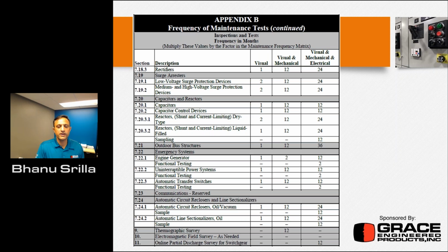So how does normal operation affect operator or maintenance staff PPE requirements? I'm not going to dwell on this specific thing in detail, but I'm going to give a simple analogy, right? If the doors are closed and you're performing a task, like taking a measurement on a meter, that's normal operation, if you meet all 6 conditions outlined in NFPA 70E, right? And if you're opening the cabinet and performing a task in an energized condition, that's a totally different task. That's the difference I would like to create.